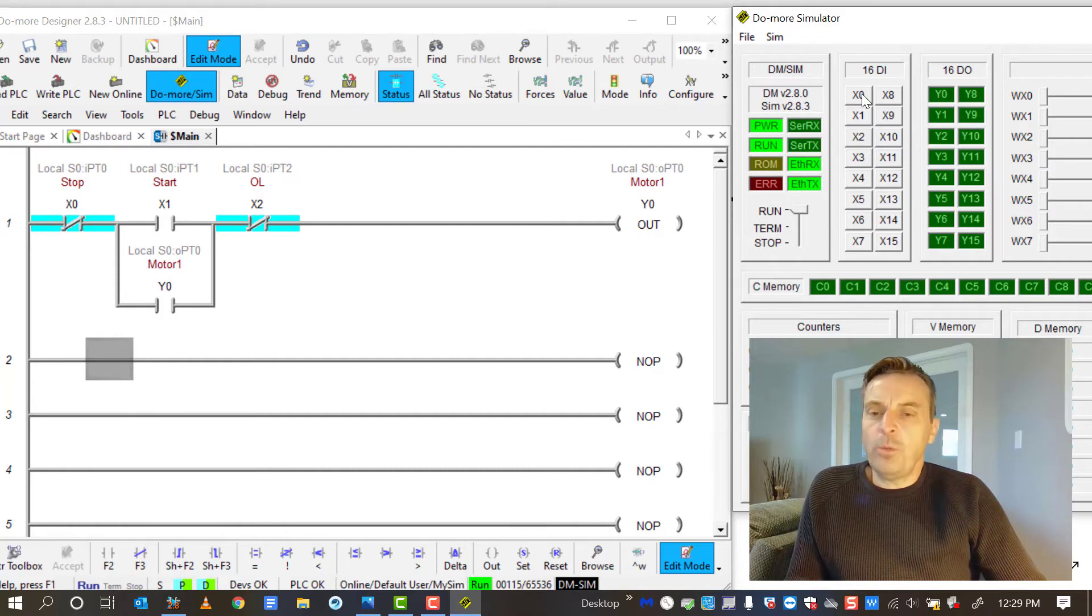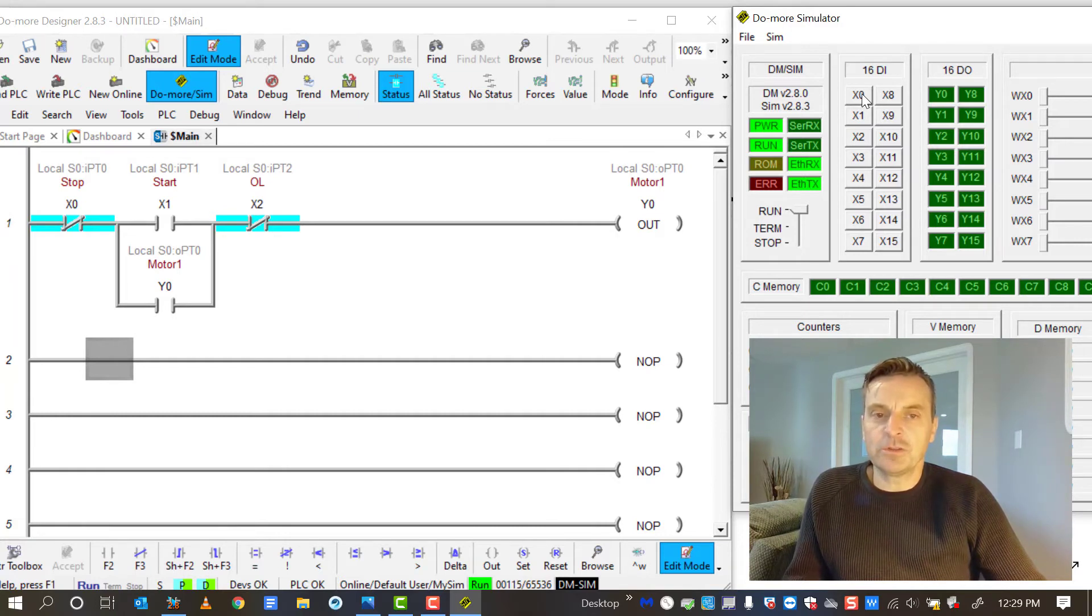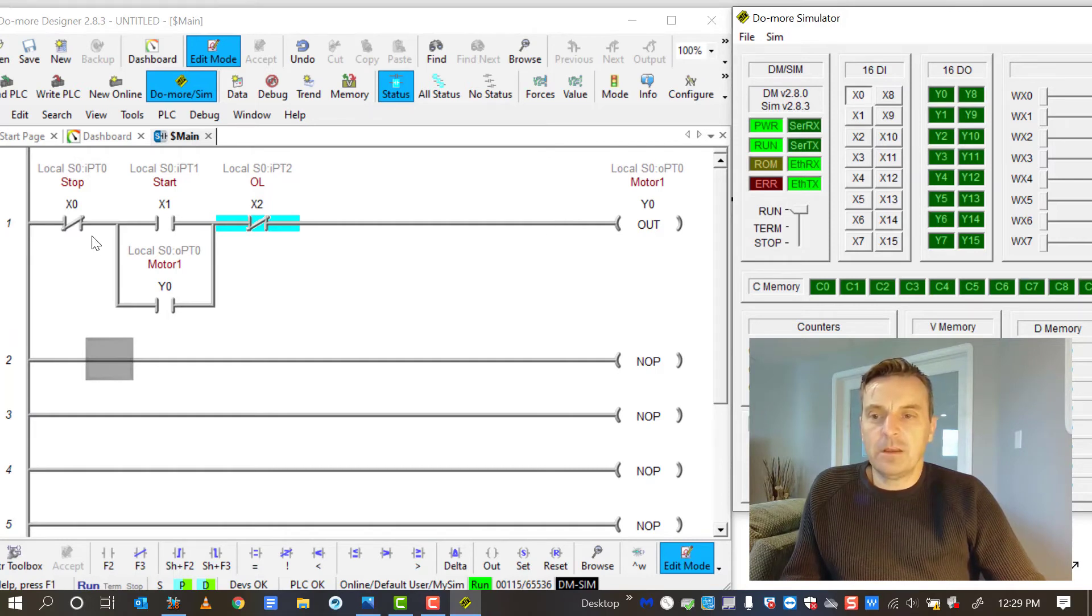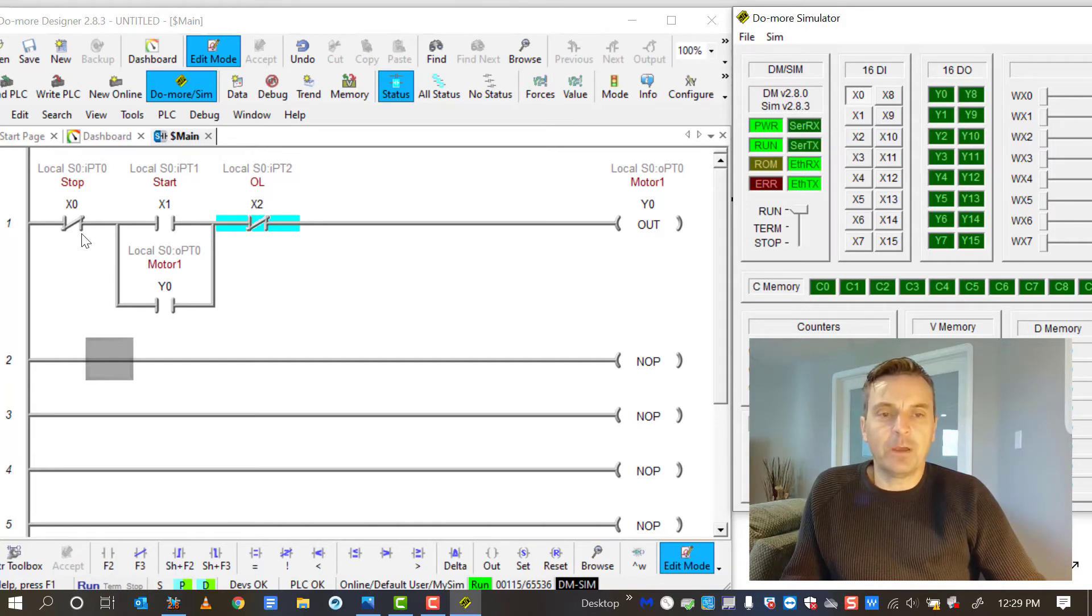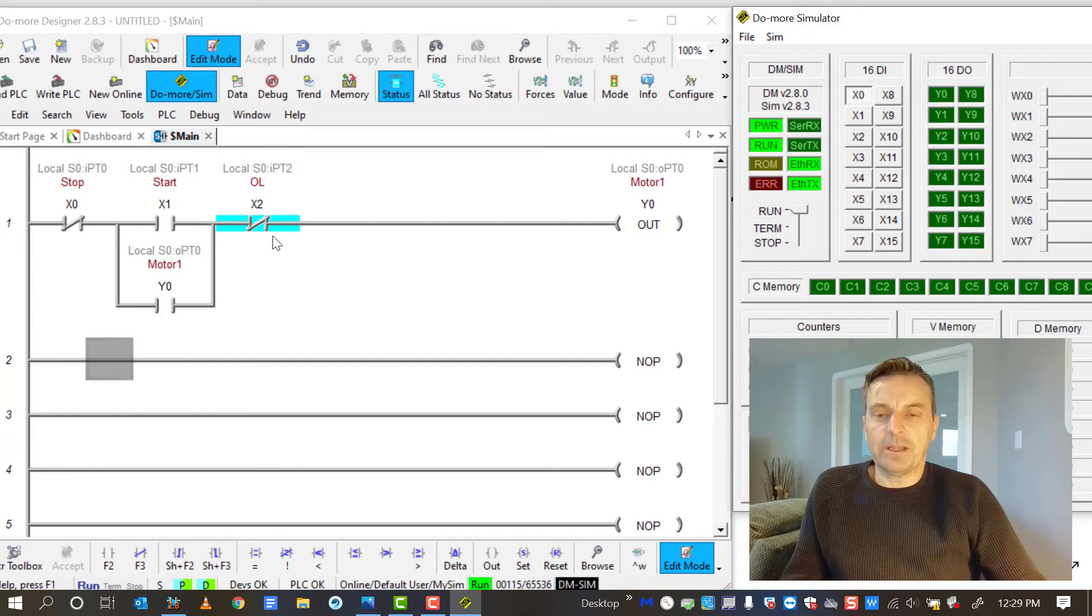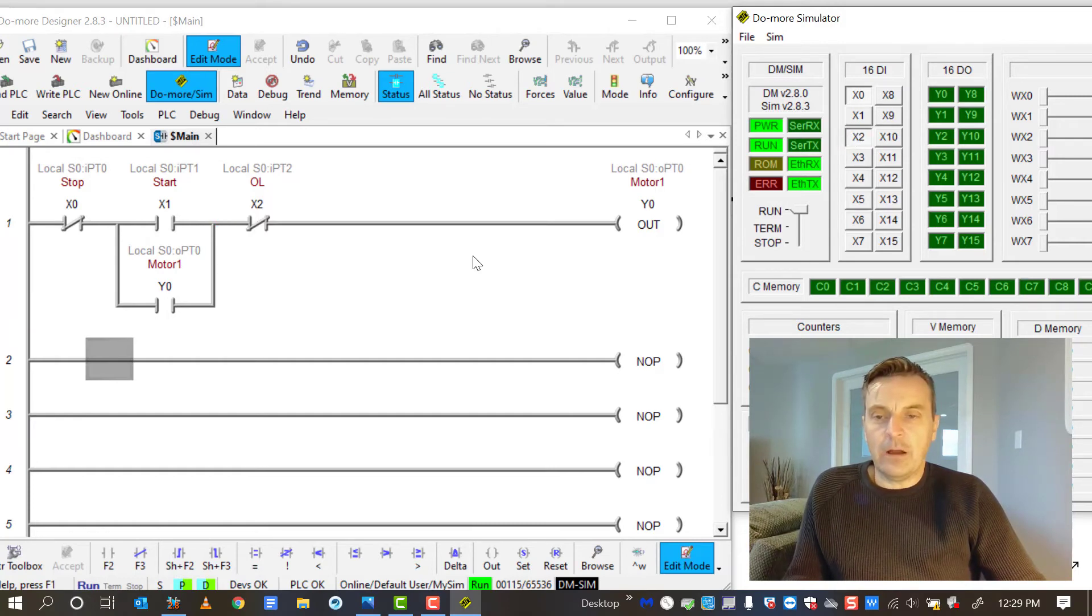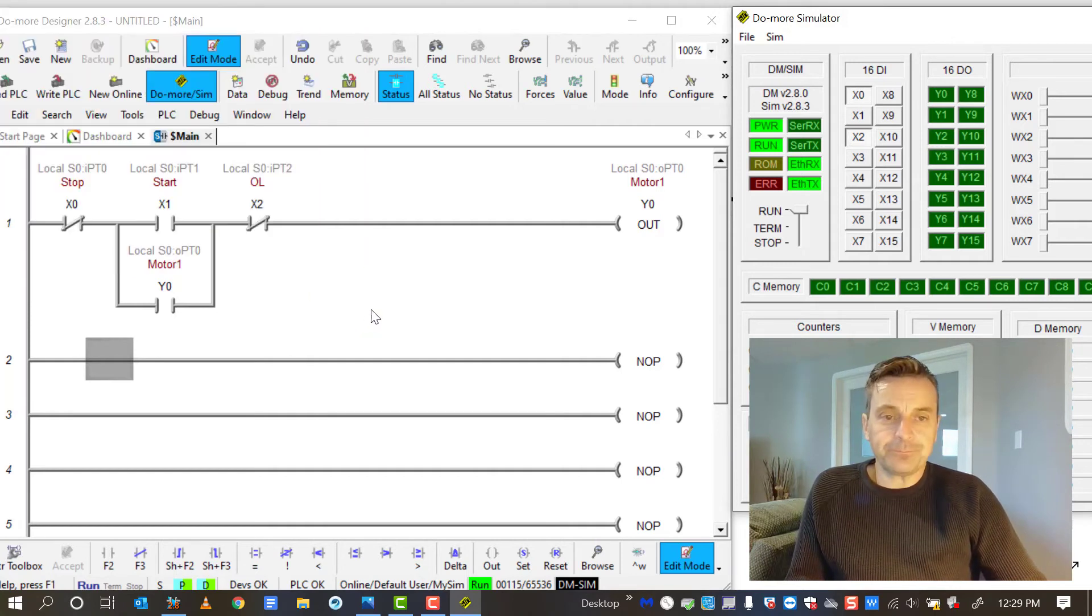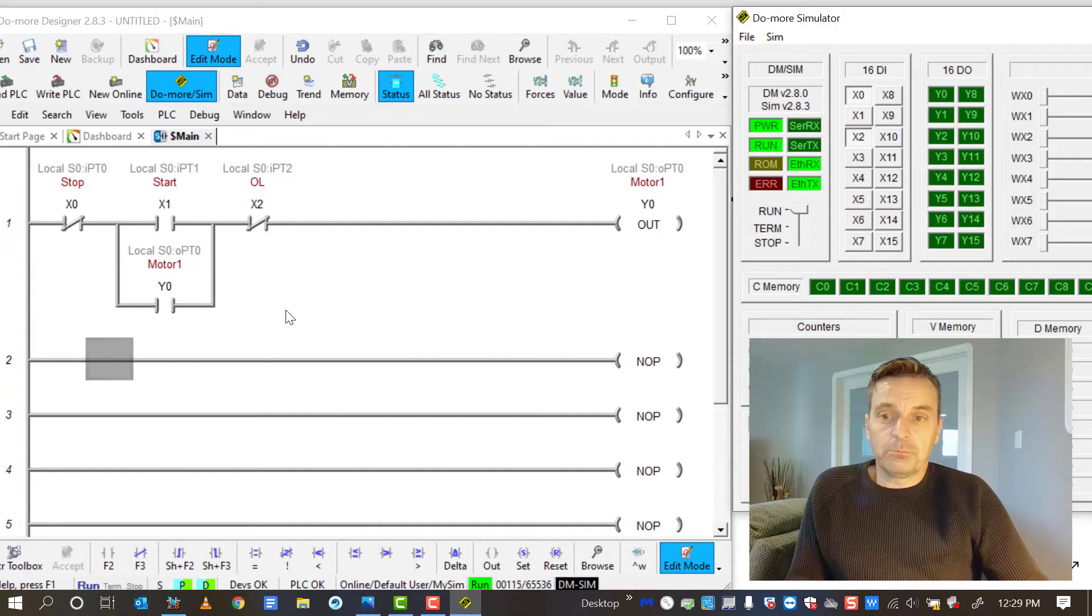X0 is open at this point. Well, if I go back to my schematic and my stop button, that was supposed to be a closure. That was supposed to be a closed switch. So let's close that switch and see what happens. Now the instruction's not happy. It's not satisfied, the instruction has not been met. What about X2? That was a normally closed overload contact on the overload block. Let's close that. Oh, now all of a sudden its instruction isn't met. It's not satisfied either.